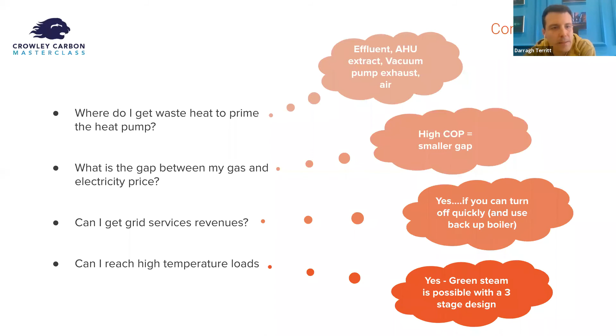Ideally, you want as high a COP as possible. You'll find COPs currently running between 2 and 6, depending on the configuration of the heat pump and the gap between the two temperature levels. That consideration is probably the most key for me to getting an acceptable payback. Thirdly, leveraging the heat pump to access grid level services, which Colin will go through in more detail later. And lastly, can you use the heat pump to generate high temperature outputs, like steam? So if you want to go to the next slide, please, Colin.